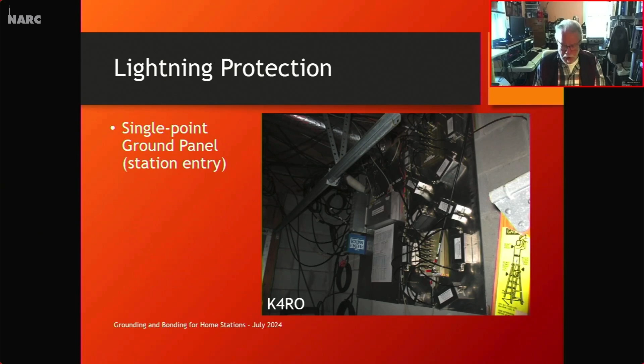Here's another example of a very small single-point ground panel, at the base of one of my towers. I have three 60-foot towers on a relatively exposed point here in the middle of the United States. At the bottom of each tower is a surplus fiberglass electrical box, and I mounted antenna switches on it, along with gas discharge tubes right here for my rotator control line, and the antenna switch here, all mounted on a simple piece of aluminum flashing inside the box.